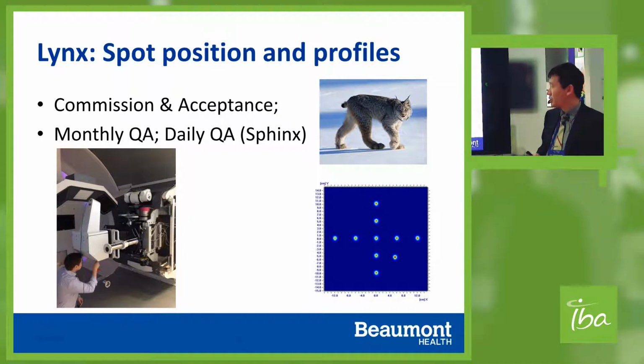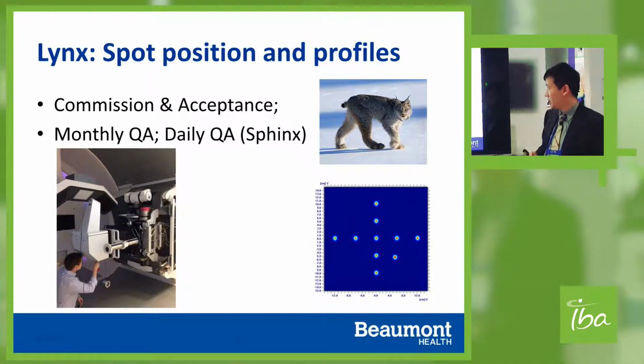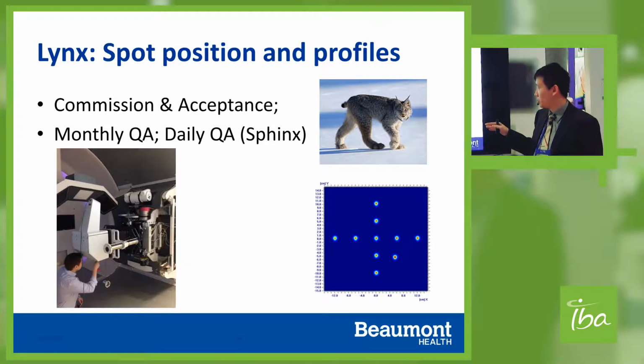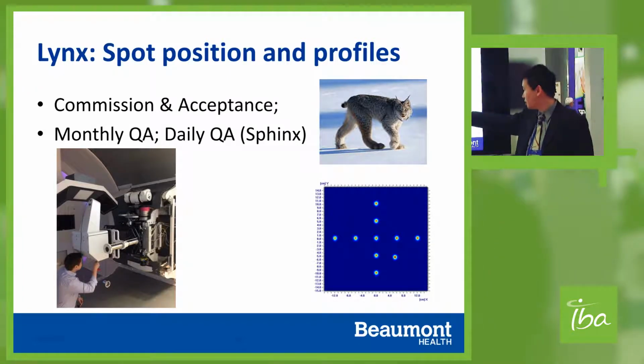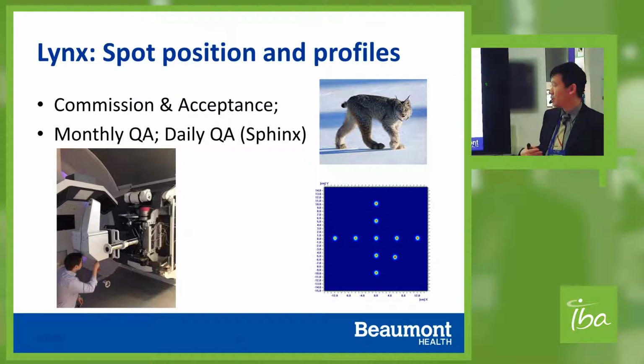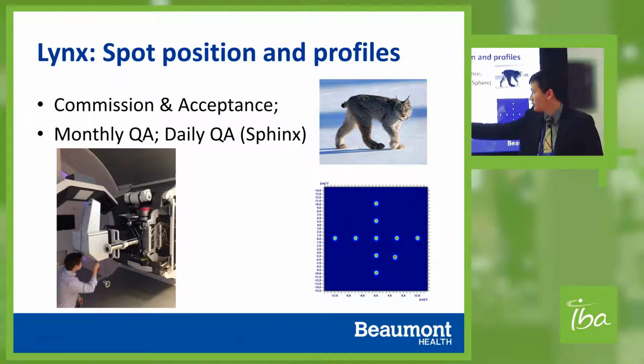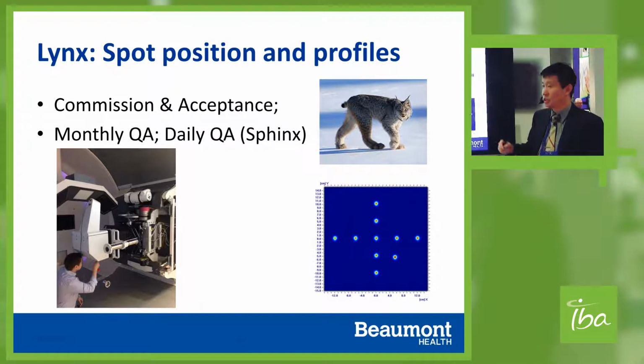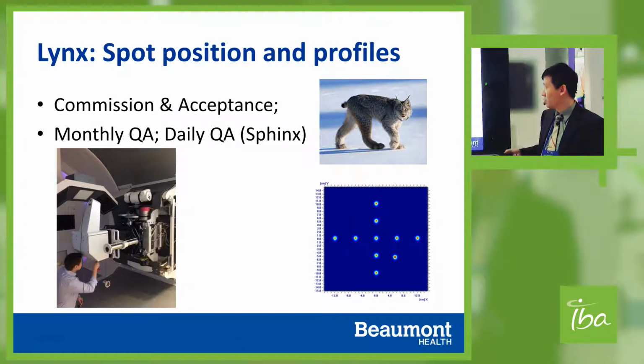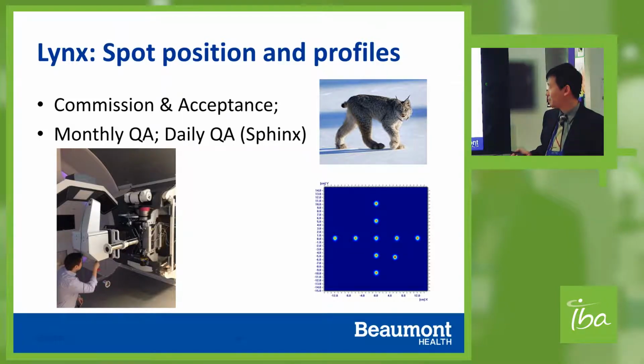So we use that for the commissioning acceptance. That's the requirement. It has a large field of view, more than 40 by 40, so we can collect all the 30 by 30. So we can collect all different spot positions and the profiles and analyze to get a nice impression of the machine performance. So this is one of the engineers mounting the Lynx on the gantry so it can rotate through the gantry and check the spot position and the profiles. So we recommend using this in the daily QA when you combine it with the Sphinx, and you can use it for the monthly QA.